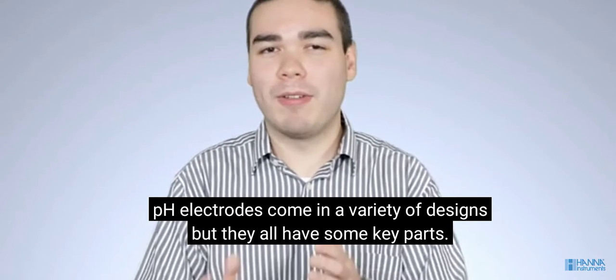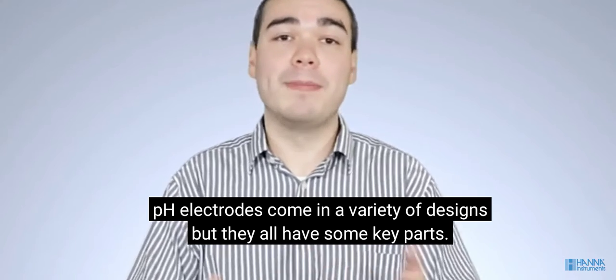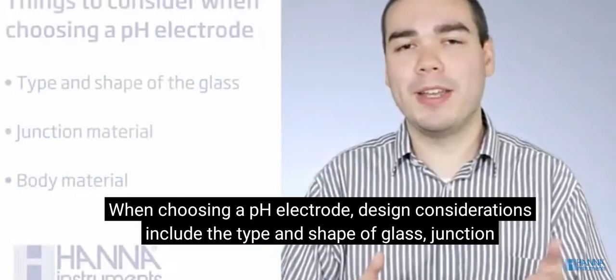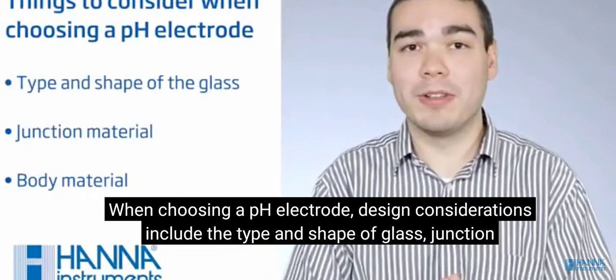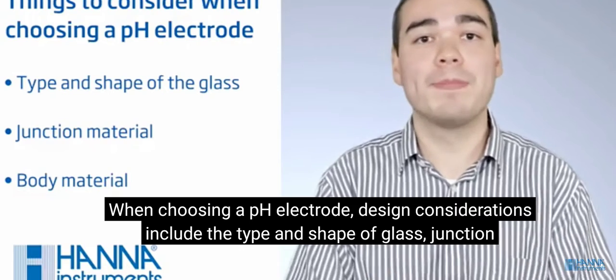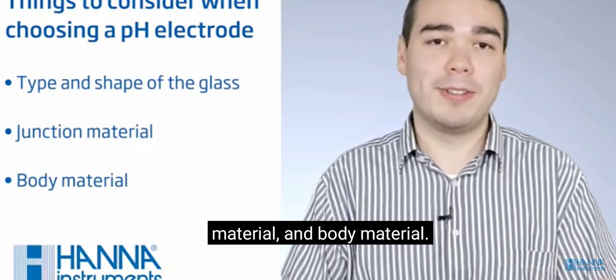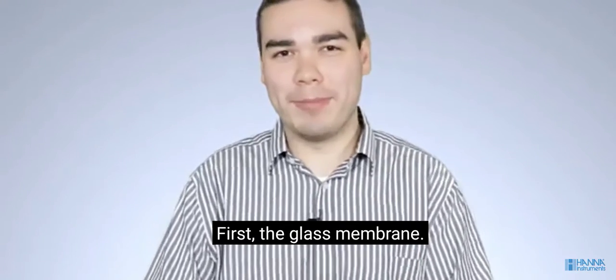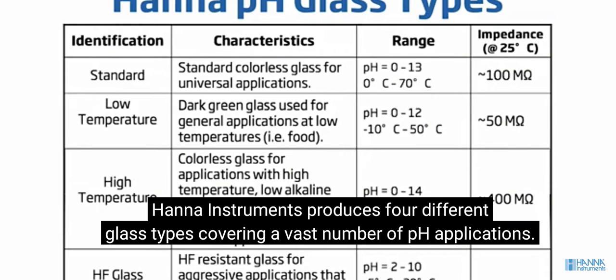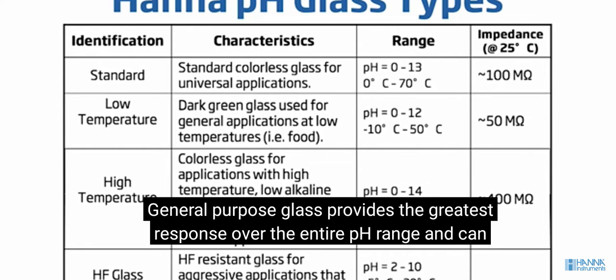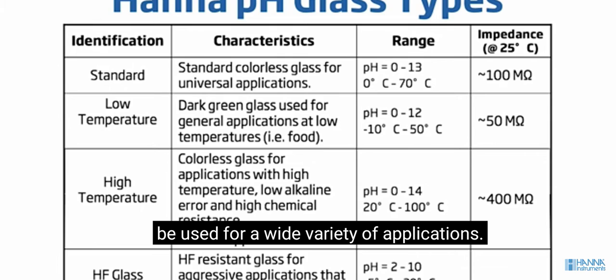pH electrodes come in a variety of designs, but they all have some key parts. When choosing a pH electrode, design considerations include the type and shape of the glass, junction material, and body material. First, the glass membrane. Hanna Instruments produces 4 different glass types covering a vast number of pH applications.